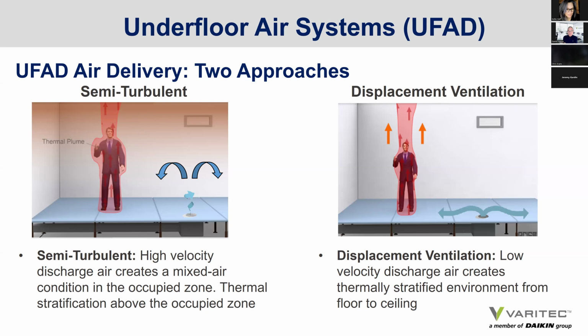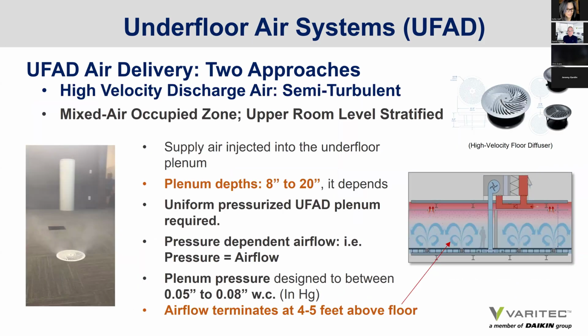There is also a displacement ventilation solution that uses more diffusers with lower airflow that actually spreads the air out along the floor to create a thermally stratified environment throughout the full height of the space. Now, ASHRAE 62.1 recognizes a 1.2 ventilation effectiveness for both the semi-turbulent design and the displacement ventilation. It really is up to the owner's needs, the budget or whatever, to decide which way to go and what the overall project objective is.